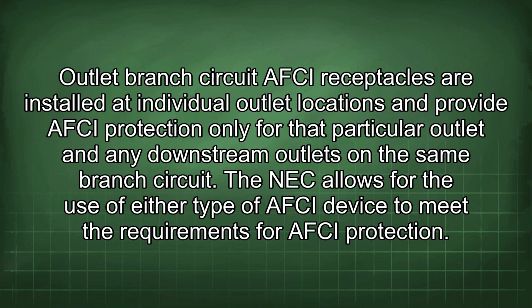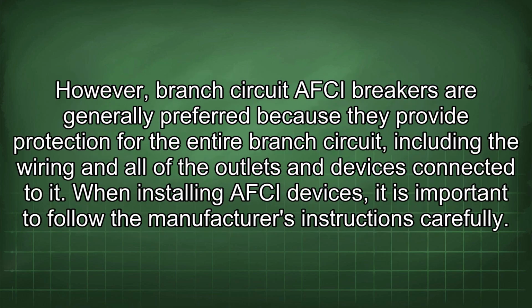Outlet branch circuit AFCI receptacles are installed at individual outlet locations and provide AFCI protection only for that particular outlet and any downstream outlets on the same branch circuit. The NEC allows for the use of either type of AFCI device to meet the requirements for AFCI protection. However, branch circuit AFCI breakers are generally preferred because they provide protection for the entire branch circuit, including the wiring and all of the outlets and devices connected to it.